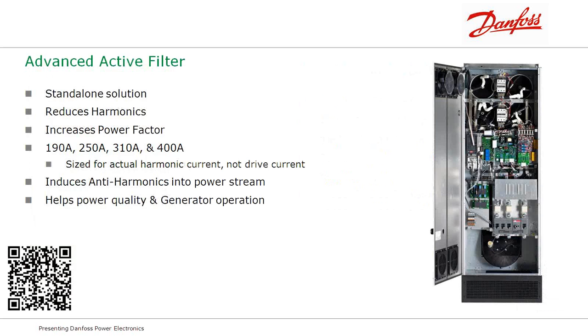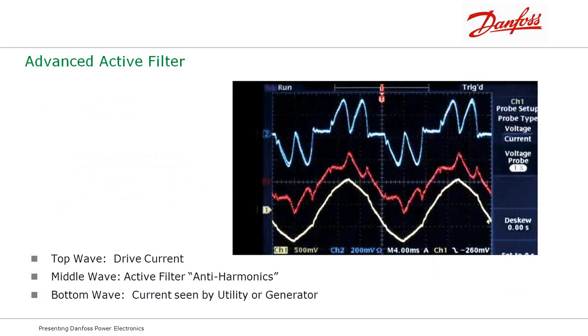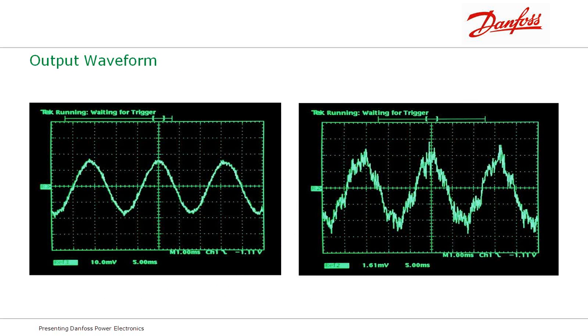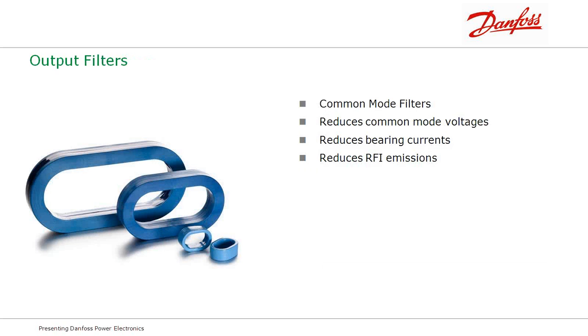Power factor correction also inside of there, utilizing here the active filter that allows you to reduce the electrical harmonics in the power distribution systems down to below 5% voltage distortion, typically about 1.6% voltage, and power factor running about 0.98, 0.99, depending on the size of the system. So one of the other advantages we have in the drive is the advanced waveform. Our drive allows a motor to be mounted up to 1,000 feet away, and we still can maintain control and rotation of the shaft of the motor.